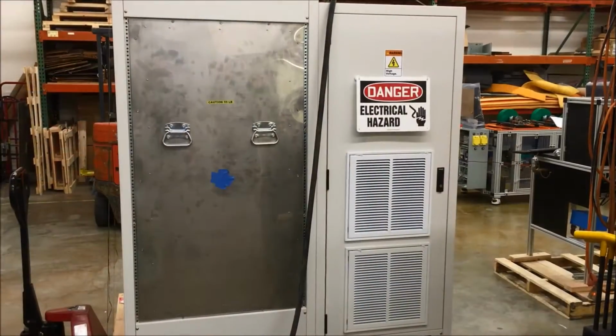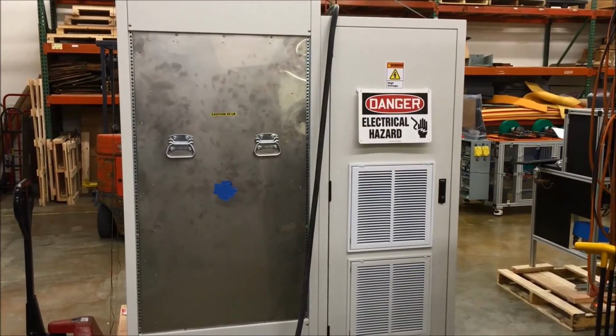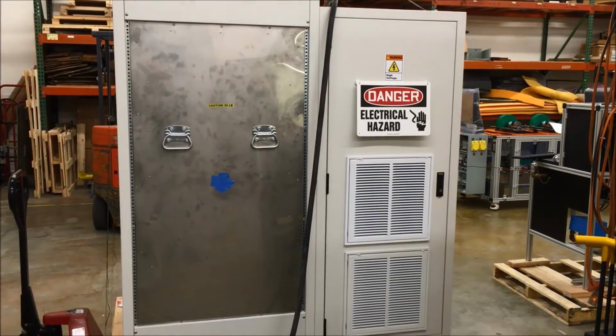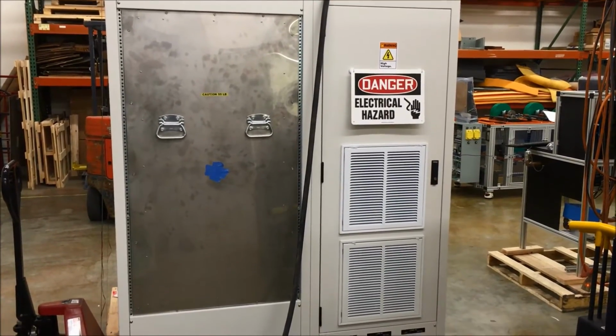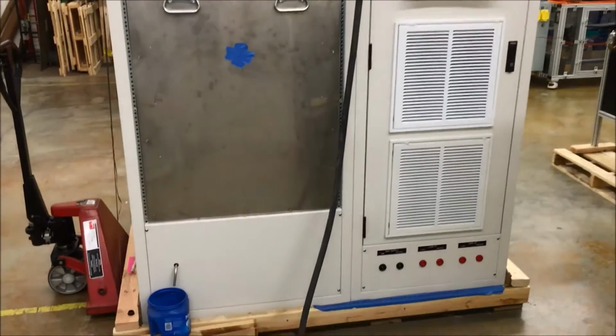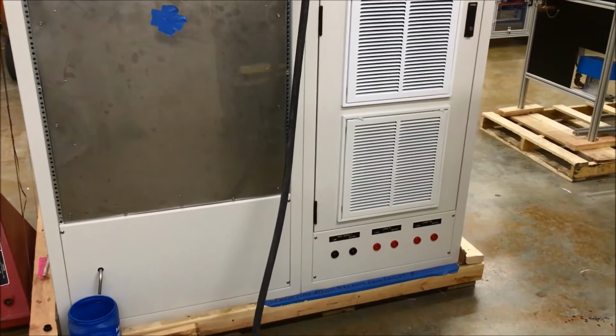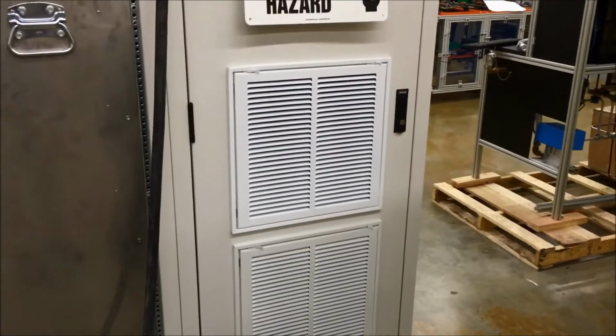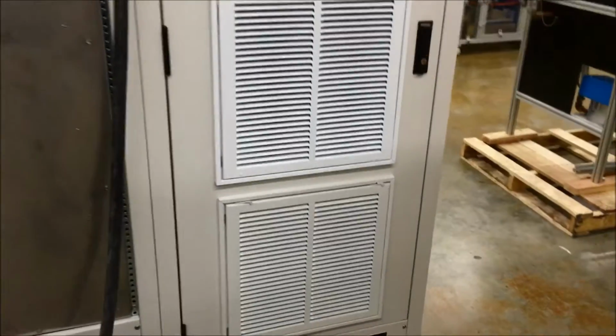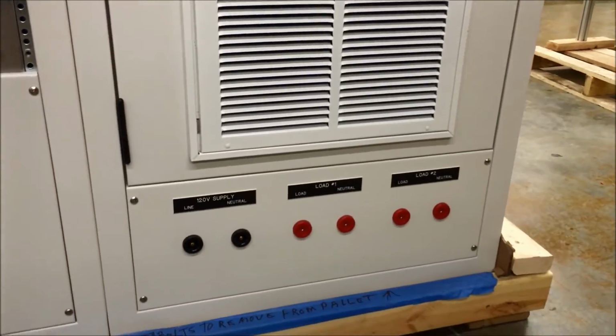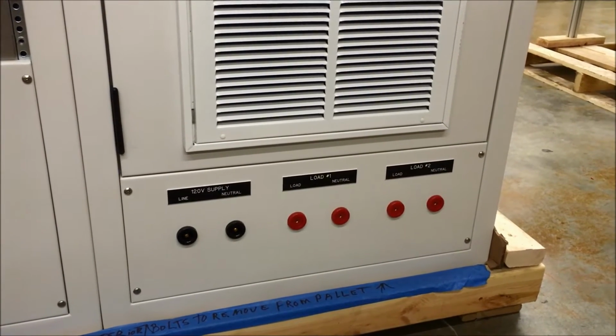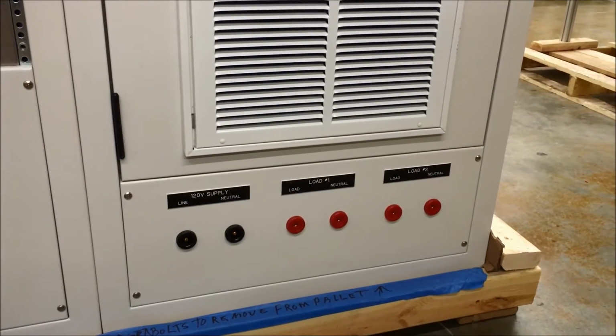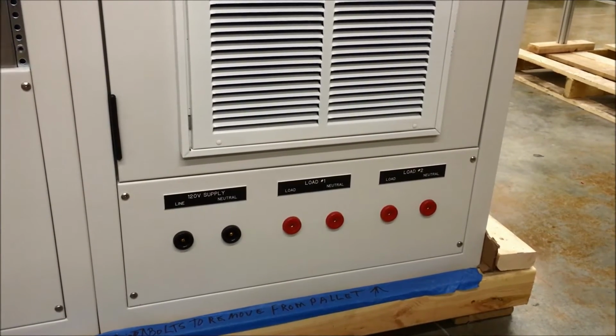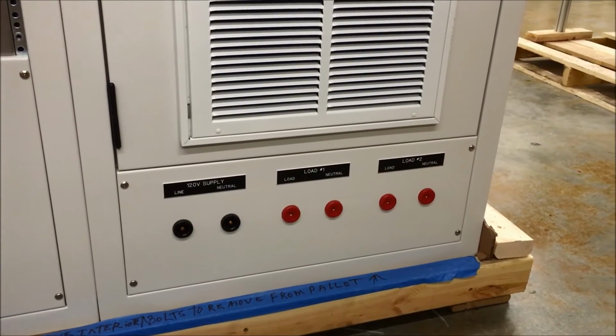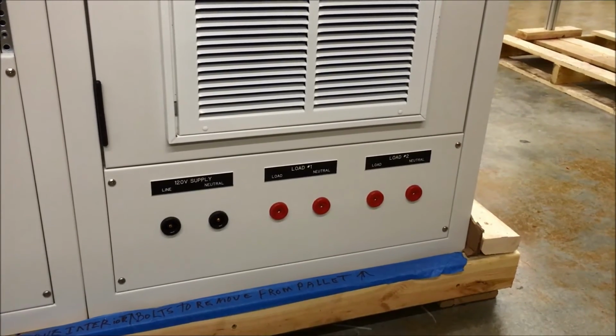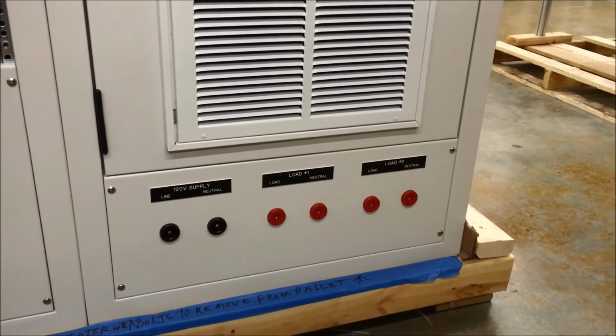Just a quick view of the back of the unit with one of the panels removed. You can see the inner thermal chamber, which is all stainless steel, as mentioned before. There's a drip tube for condensate out of the bottom, a couple of air intakes for the compressor, and the ability to add external loads so that you can run a full line voltage, line current thermostat in the chamber without any worries about the voltage or the current. I do believe this particular unit can take up to 50 amps.